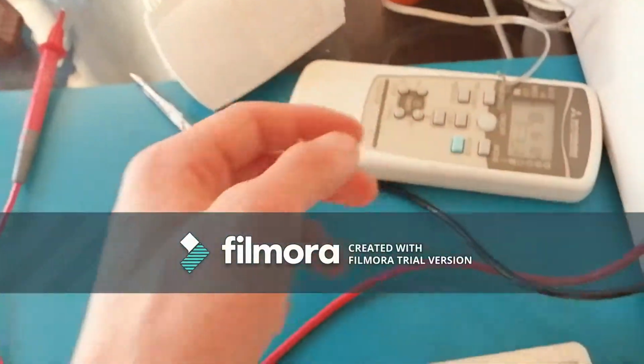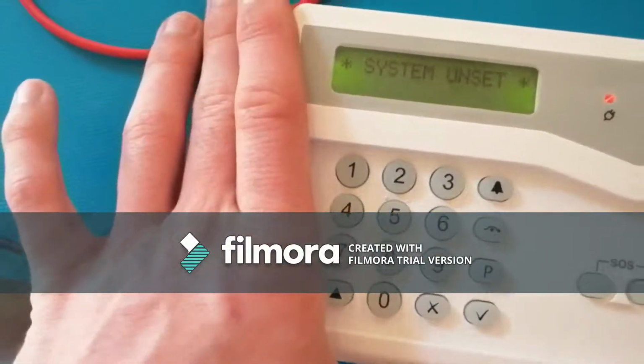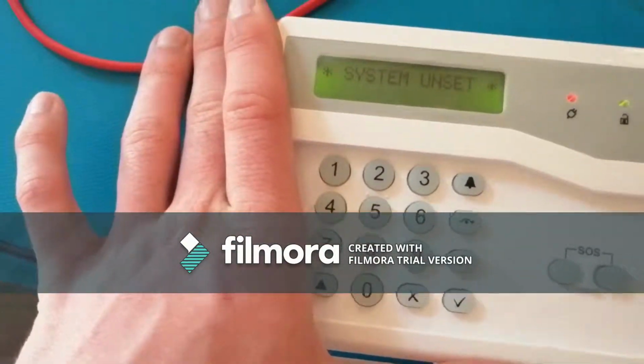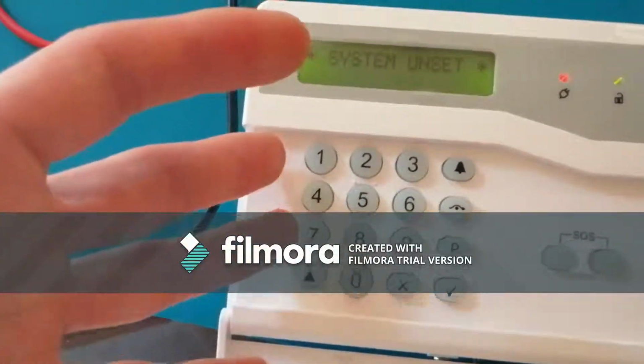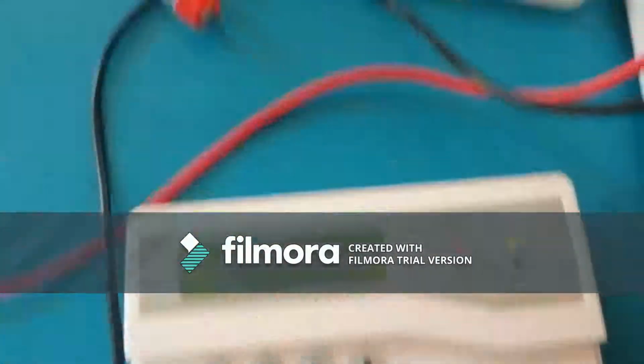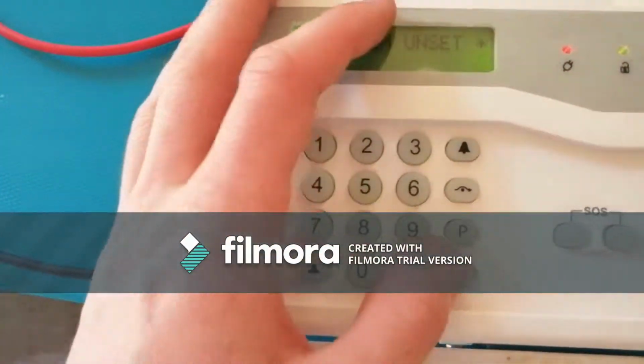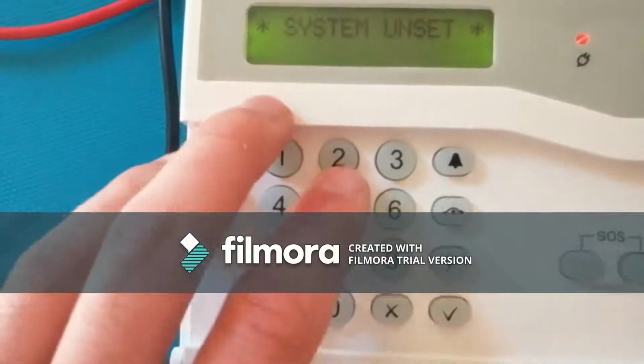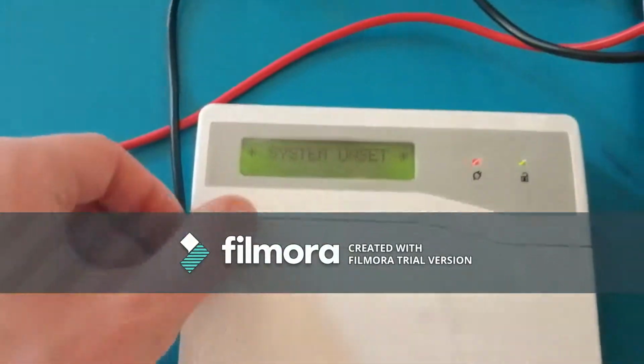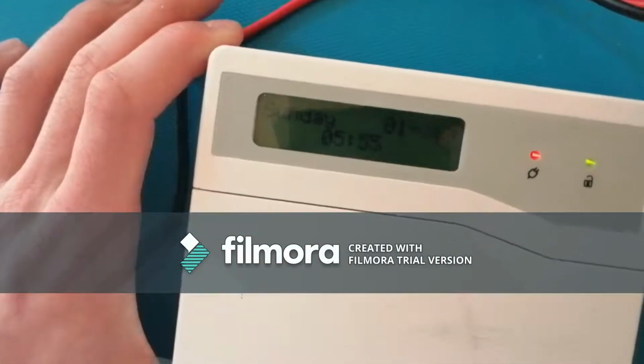Although if it is a door contact, if it's your front door and you isolate that, then you will not be able to set and unset the system. It just won't work properly, to be honest. But if it's a PIR, then you can omit that and it will work. It will set and unset and it should be fine. Okay, so that's the engineering method.